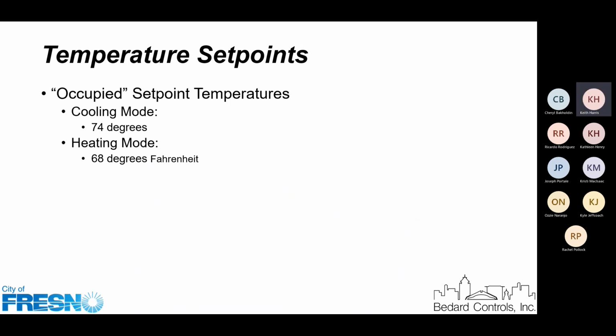So if it's in heating mode, you'll get the rising steam icon. You'll be able to use the up and down arrows to the point where you get to 68 degrees and then it'll stop, but you could be less. And some of your colleagues in other buildings like it cooler than that. But those are the two set points that were set up for this particular project.